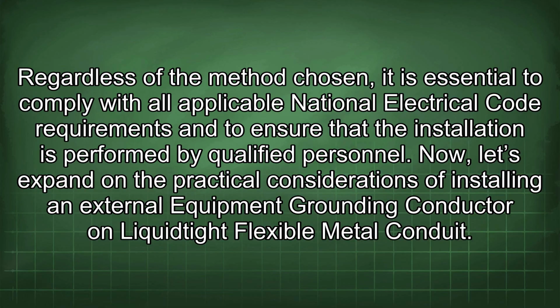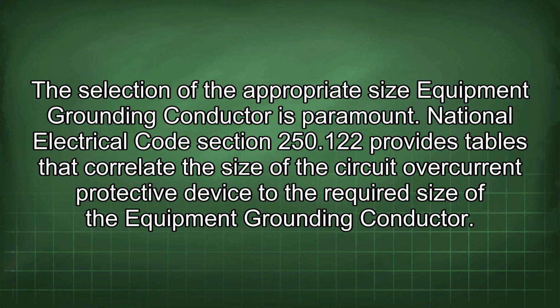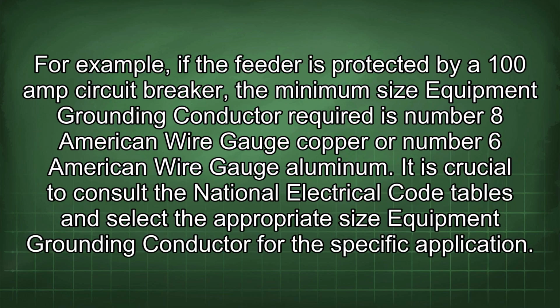Now, let's expand on the practical considerations of installing an external equipment grounding conductor on liquid-tight flexible metal conduit. The selection of the appropriate size equipment grounding conductor is paramount. National Electrical Code Section 250.122 provides tables that correlate the size of the circuit overcurrent protective device to the required size of the equipment grounding conductor. For example, if the feeder is protected by a 100-amp circuit breaker, the minimum size equipment grounding conductor required is number 8 American wire gauge copper or number 6 American wire gauge aluminum.